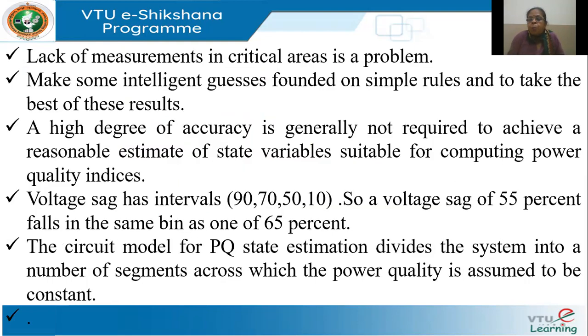So what are all the issues here? Let us see. The first one is that lack of measurements in critical areas is a problem. If you cannot have good measurements, your estimates also will not be correct, right? So I should know where I should put the minimum monitoring equipment. Supposing there are 100 state variables of interest, and I want to put 50 instruments. Out of the 100, which 50 should I measure and which 50 should I estimate? Which of these measurements are critical? If I don't put monitoring equipment at the critical areas, then my estimations may not be correct. And we may have to use some kind of an intuitive rule to get the best results.